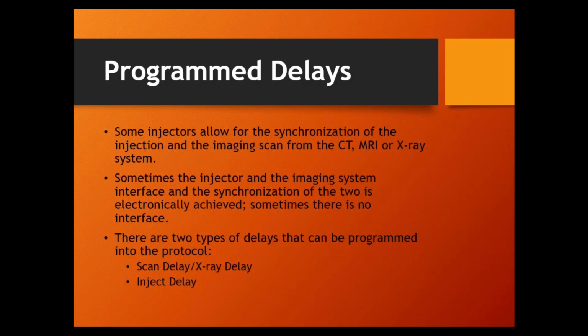And the other way goes by 2 different names. There's X-ray delay and there's scan delay. For angio injectors, it's generally called X-ray delay. We'll program in an X-ray delay. So many seconds, and that same exact thing. Hit the buttons. The injector starts injecting, the imaging system starts imaging. Okay? That's just for angio. It's called X-ray delay.